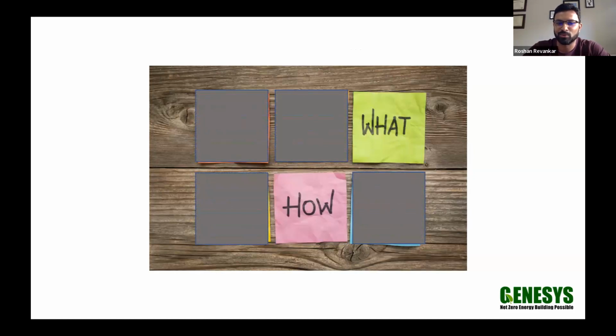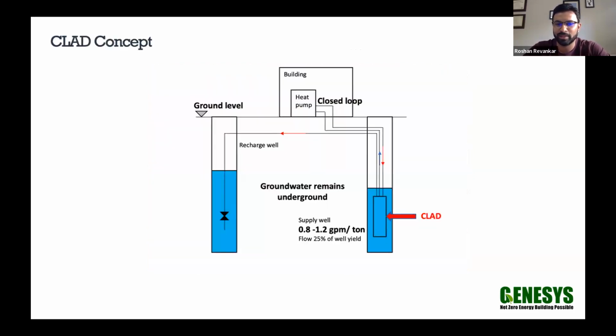Most of the rest of the slides is about what and how. What is CLAD and how is it going to be implemented? Just a very, very basic conceptual diagram of what CLAD is. I'll spend a good couple of minutes on this slide. As you can imagine, it is a closed loop system. We call it closed loop advection device. Typical building with a heat pump, just a schematic here. This could be multiple heat pumps or a pump station where you have two pipes, supply and return, going into the CLAD unit. So a supply and return going into the heat exchanger. The entire looping on this end is closed loop. So similar design criteria to any other closed loop system.